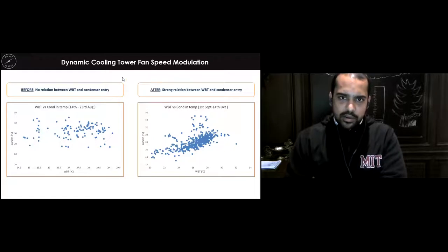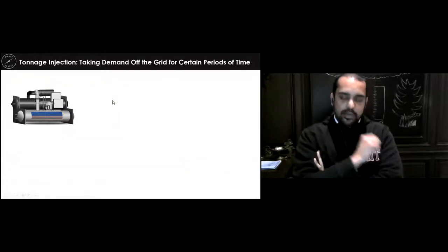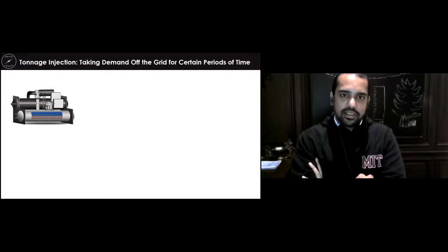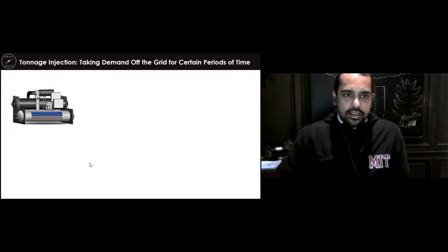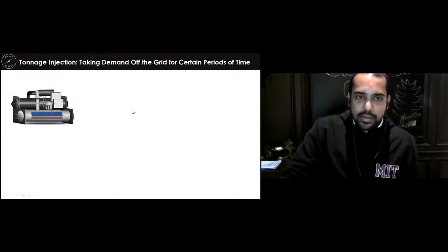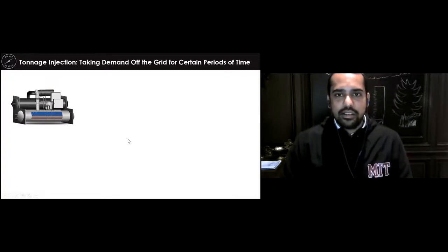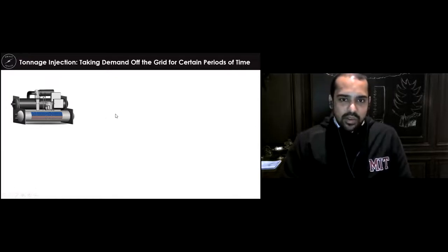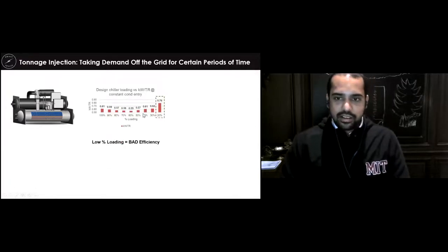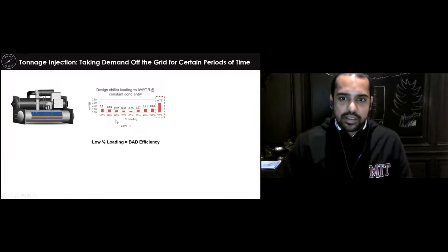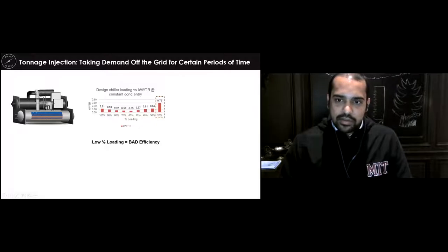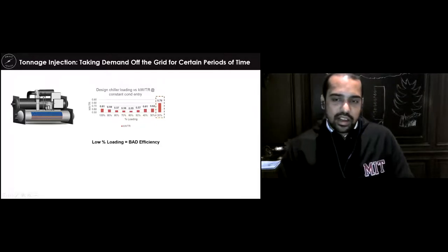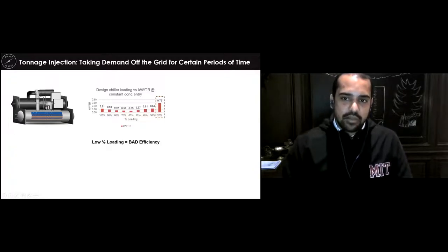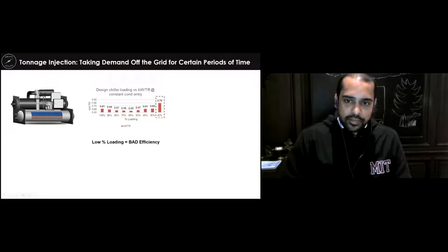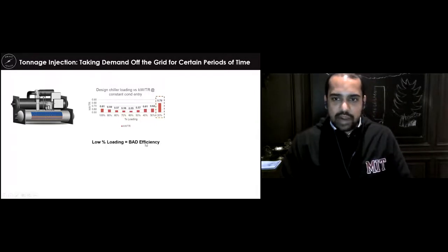The next example is the most interesting for today. This is getting closer and closer to the subject of today, which is grid interactive buildings. Here, this is something that we call a tonnage injection. It started as an experiment, but now it has become a standard energy management measure. If you look at a chiller, this is a performance curve of a particular chiller. These equipment don't perform at the same efficiency under all conditions. They have different curves. What this shows is that when the loading of a chiller becomes very low, let's say it's only 20% load, like late evenings and winter times, the efficiency of the chillers is not very good. They consume more power for every ton of cooling that is produced by this chiller. So low percentage loading means bad efficiency.